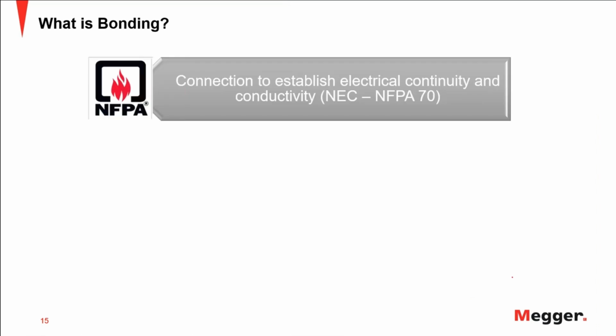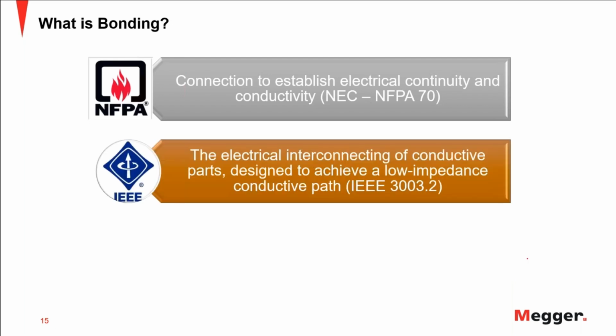So if we look at the NFPA documents, bonding is a connection to establish electrical continuity and conductivity. It's a very broad definition, and it gives you a very good idea. However, the IEEE definition says that electrical bonding is the electrical interconnection of conductive parts designed to achieve a low impedance conductive path. So this for me is kind of a key. You want to have a low impedance conductive path, and if you're talking about low impedance, you're also talking about conductivity.